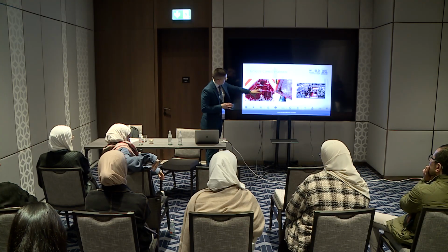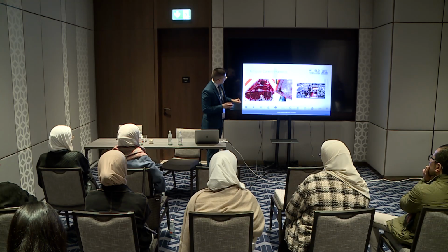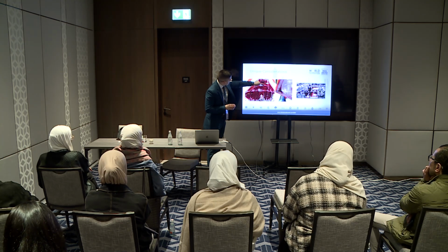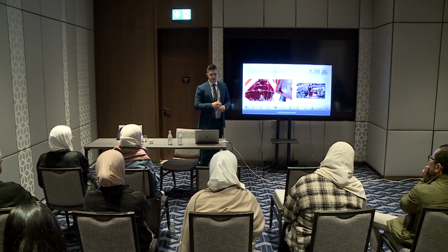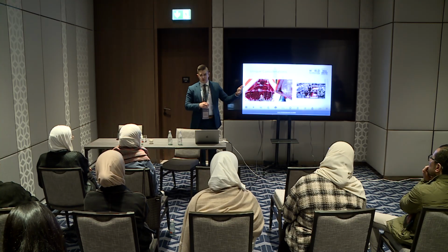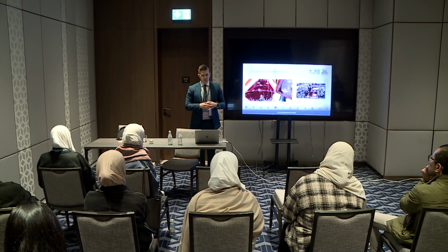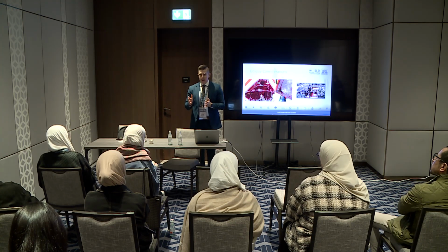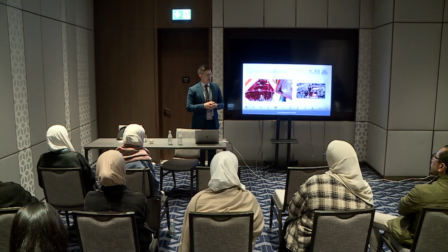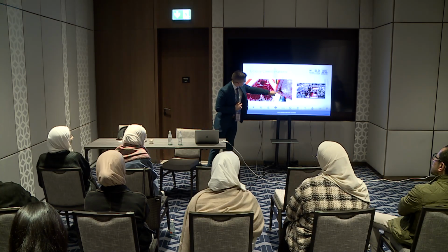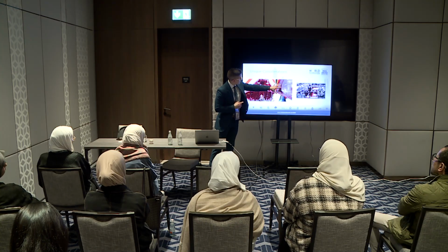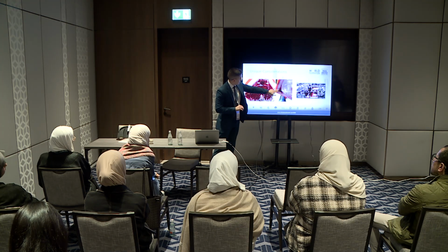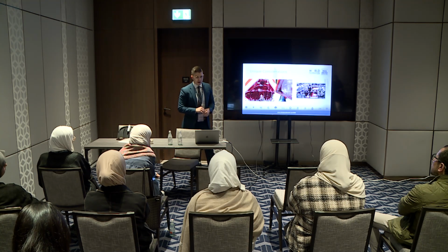Here you can see this is the oxygenator faceplate. And you can see thrombus and fibrin staining here that develops. This is most of the time actually normal and expected. This will happen during ECMO support. It's just a matter of how bad it gets and what the configuration and consequence can be. You can see just better the thrombus. This is an oxygenator after we washed it with crystalloid. So you can see all the blood is washed out, and you can see the thrombus that remain.